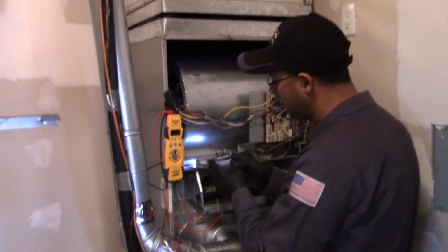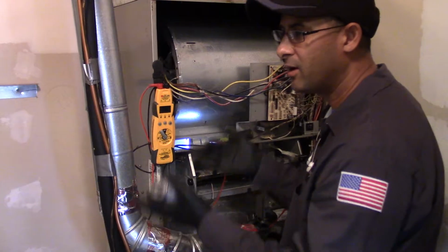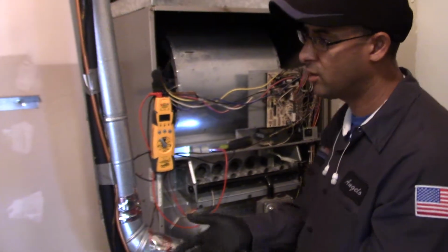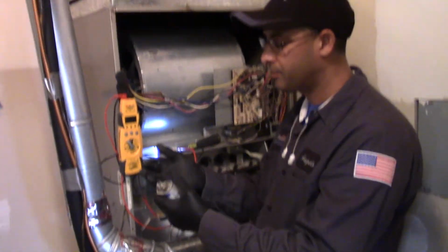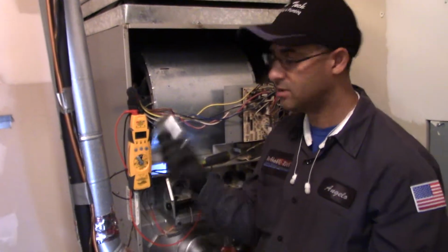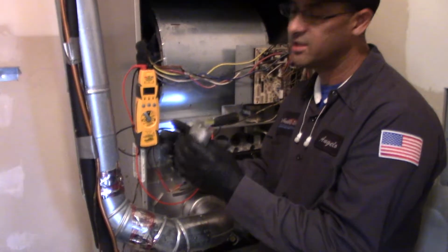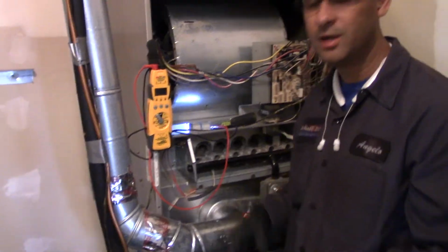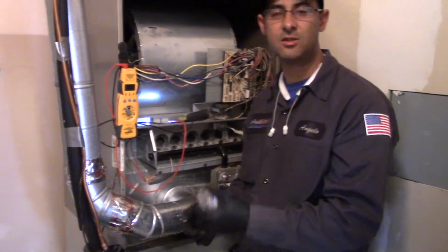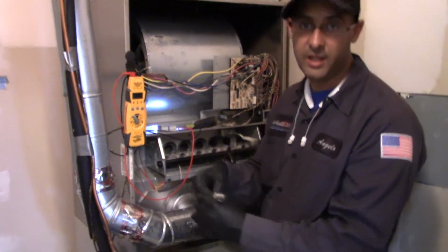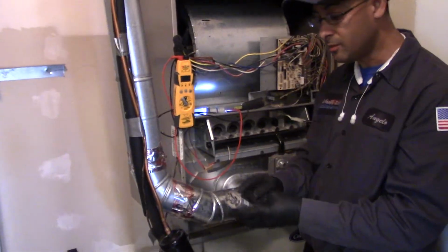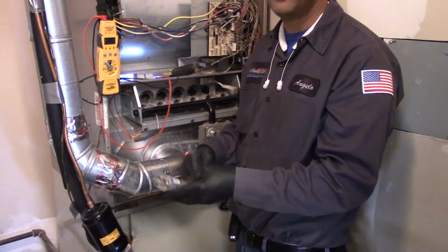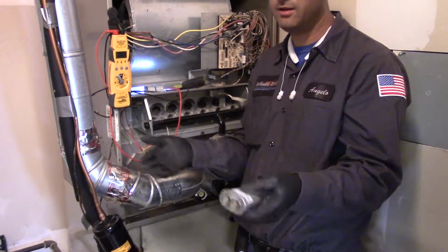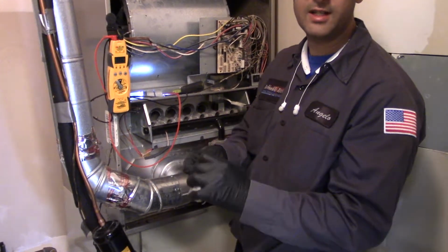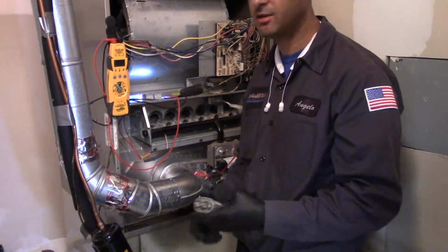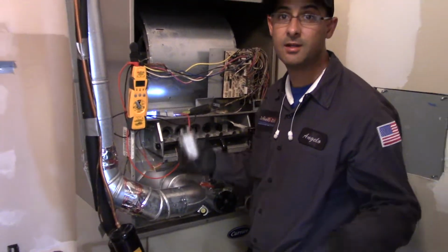But another thing we look for, typically, whenever we get a motor call or a compressor call or a fan motor call for the condenser, is whether these capacitors are swollen. They look like a soda can you put in the freezer that's going to explode. Right away you'll know the capacitor is going bad, right? Or there's oil bleed. Even if it's reading right, say it's 10 UFs and it's reading 10 UFs, or it's 15 UFs and it's reading 15 UFs, if I see oil, that's telling me the oil is leaking out of the capacitor, so I'm going to recommend a capacitor anyways.